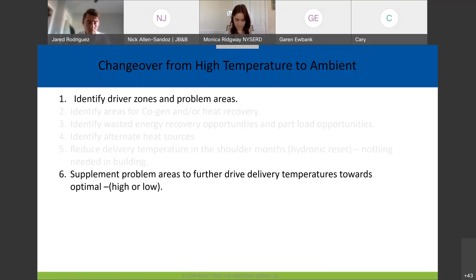So we want to reduce the delivery temperature in the shoulder months, the hydronic. Remember our bin data graph, that's 7,000 hours. We want to tailor this to that. We want to have the pumps running at the lowest speed. We want variable speed compressors in some of our distribution system on the heat pumps, so that we can turn down, and the affinity laws become our friend. So supplement the problem areas to further drive delivery temperatures towards optimal, high or low.